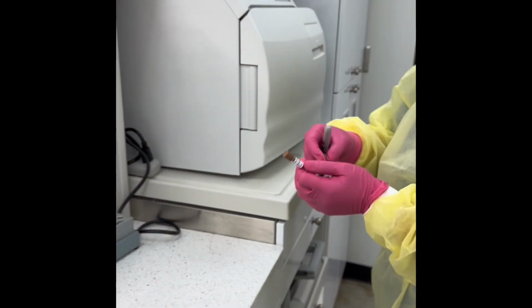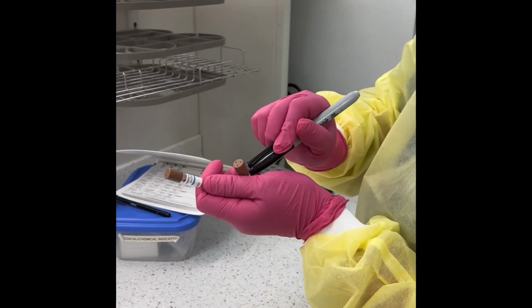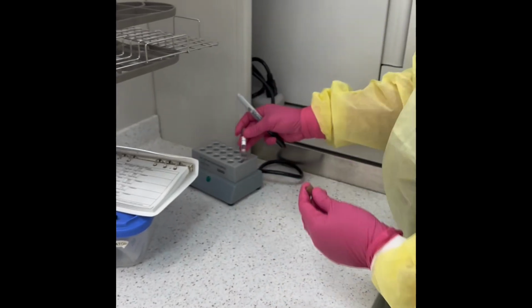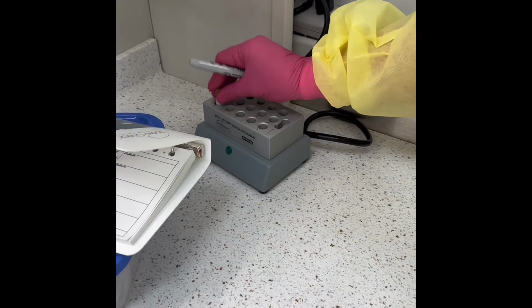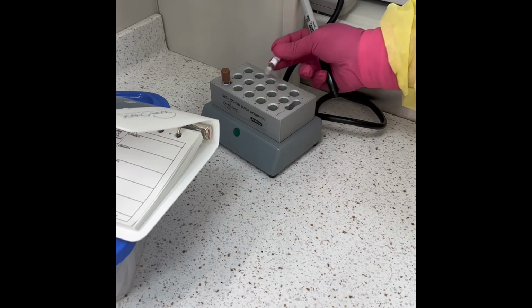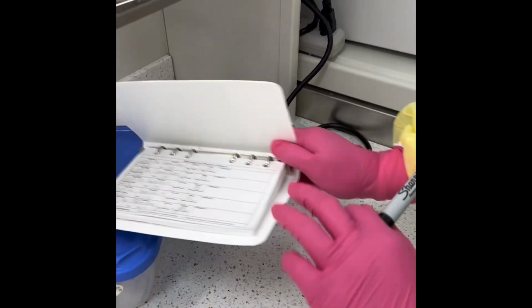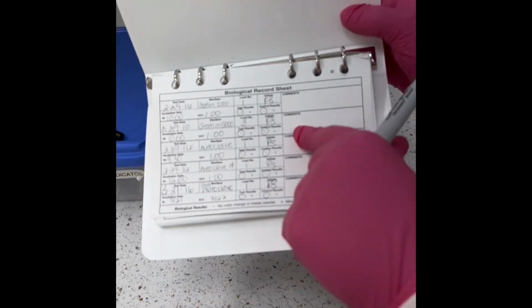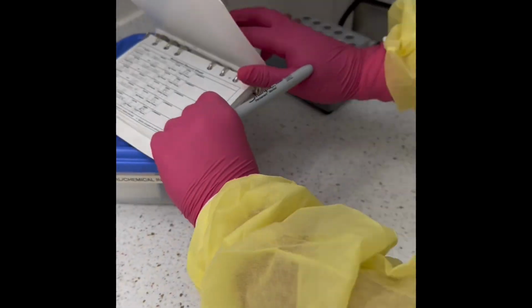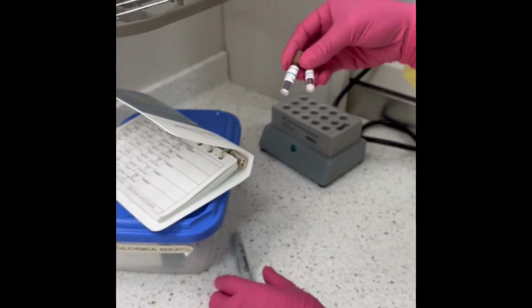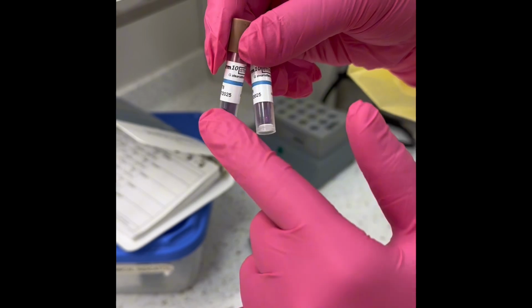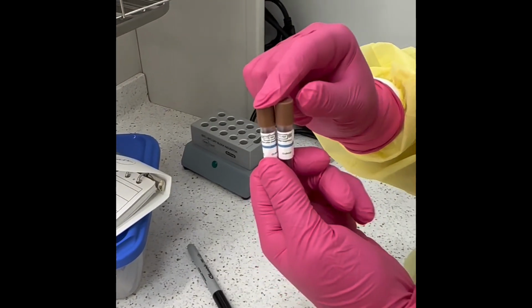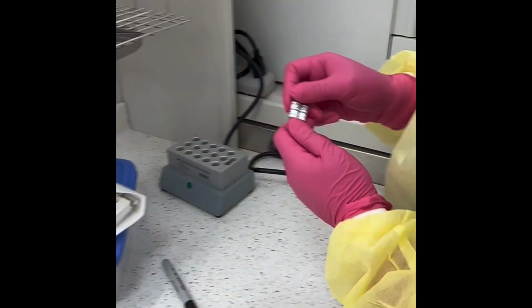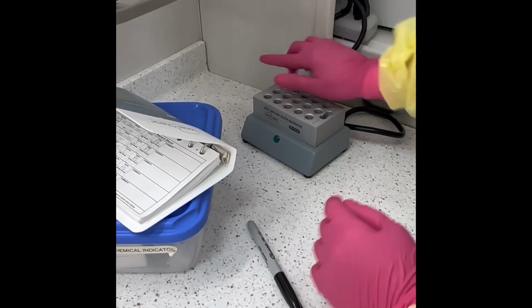Use 2 vials, one placed inside sterilizer and the other is the control vial. Label using initials, date, and load. After processing, crush the vials in the indicator's opening until you hear a pop. This allows the spore strip to be surrounded by fluid. Write down all the information. Also, write down your name, date, initials, and run of the day. Place both vials into incubation for 10 to 24 hours.